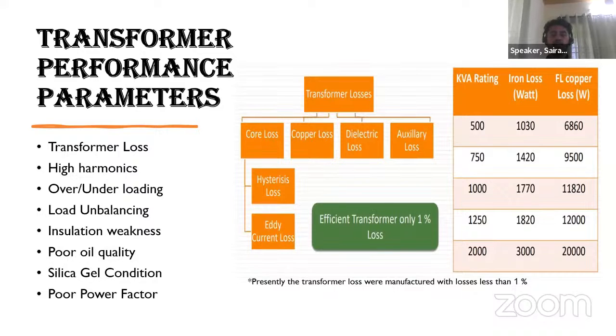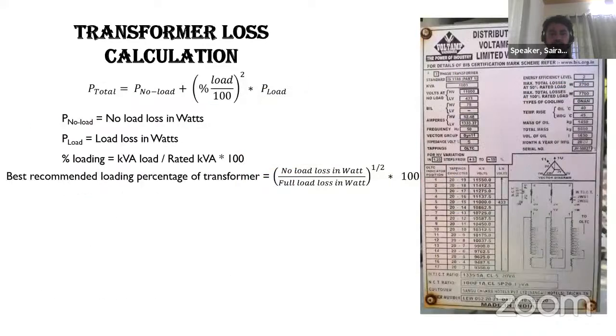Insulation, poor oil quality, then silica gel condition. If the silica gel condition is very poor, then it can't absorb the moisture in the transformer, and that will lead to tripping of the transformer also. Then poor power factor. It directly affects the demand, that is, the loading of the transformer. If the loading gets higher and higher, then the distribution transformer's efficiency will be reduced.